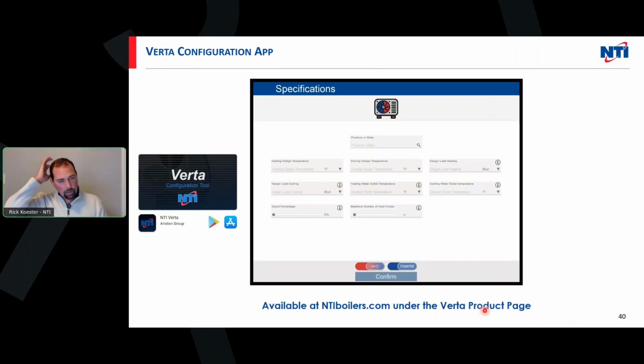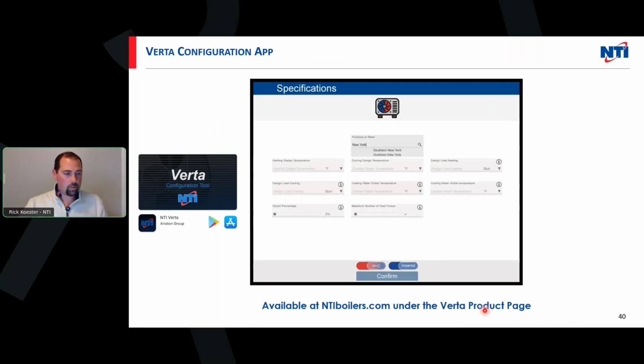Because typically when you look at a Manual J, we're heating our home, or picking the equipment, for the worst case day, which is a very small percentage. So here we can play around with that number. This is how it works: you pick your province or state. In my case, I picked New York because that's where I'm at. It gives me the option of Southern or New York, so I can put in Southern New York, and it'll get me more accurate to my weather stations.